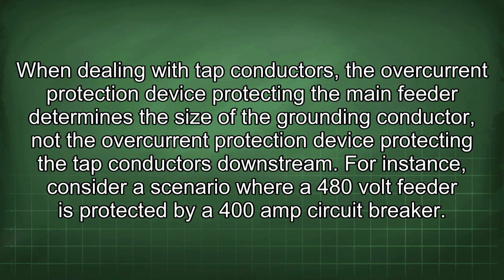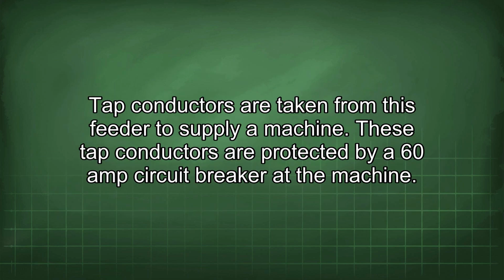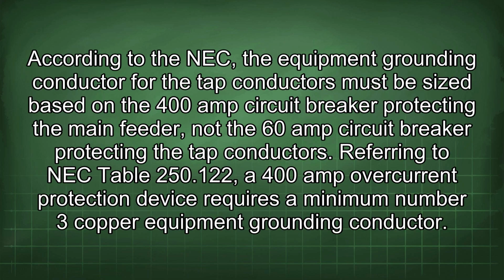When dealing with tap conductors, the overcurrent protection device protecting the main feeder determines the size of the grounding conductor, not the overcurrent protection device protecting the tap conductors downstream. For instance, consider a scenario where a 480-volt feeder is protected by a 400-amp circuit breaker. Tap conductors are taken from this feeder to supply a machine. These tap conductors are protected by a 60-amp circuit breaker at the machine. According to the NEC, the equipment grounding conductor for the tap conductors must be sized based on the 400-amp circuit breaker protecting the main feeder, not the 60-amp circuit breaker protecting the tap conductors.